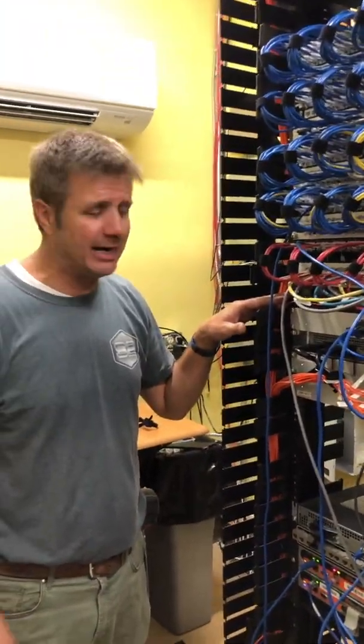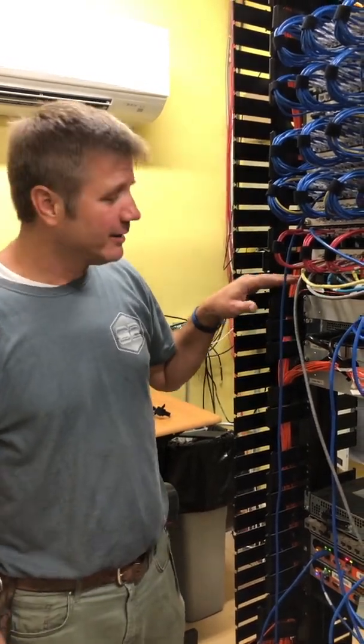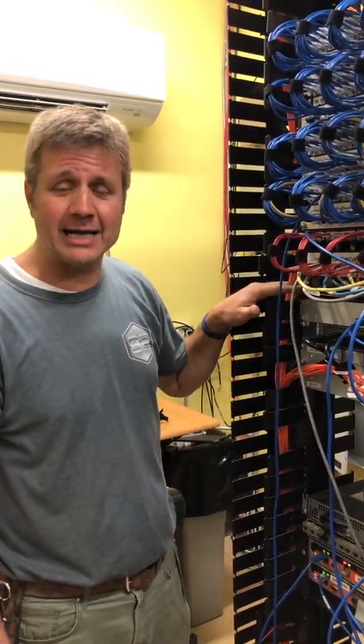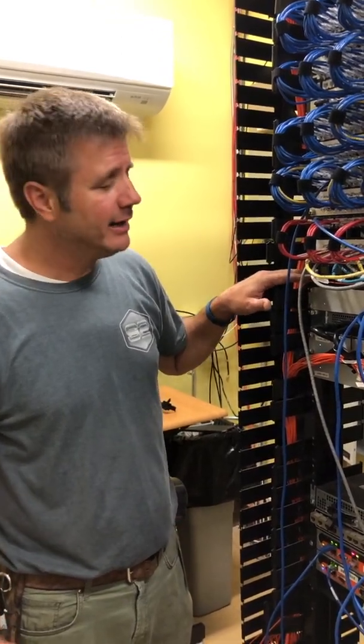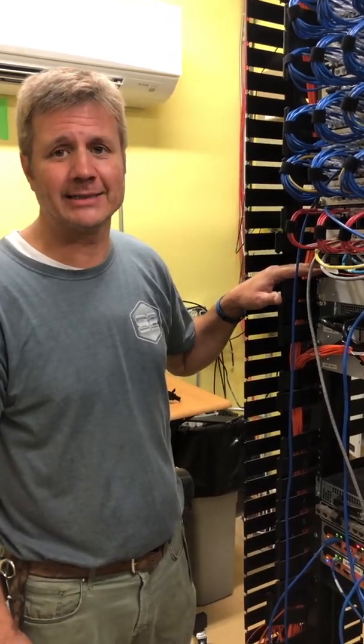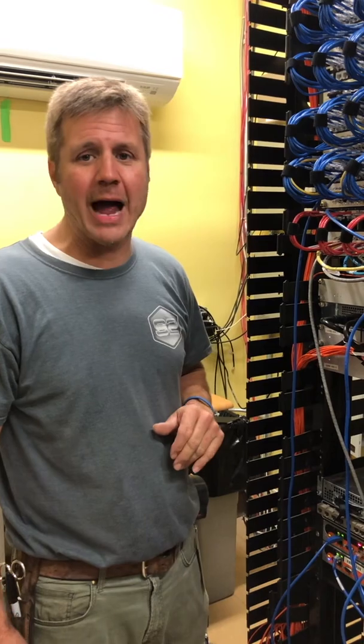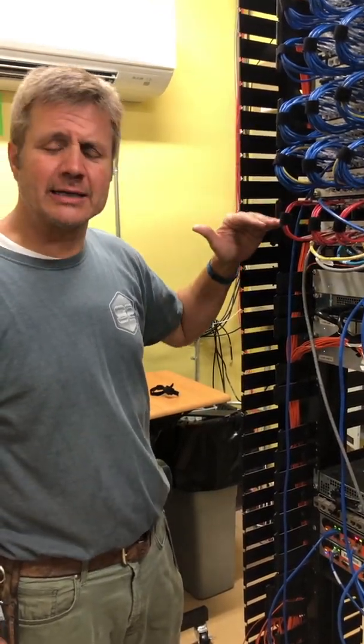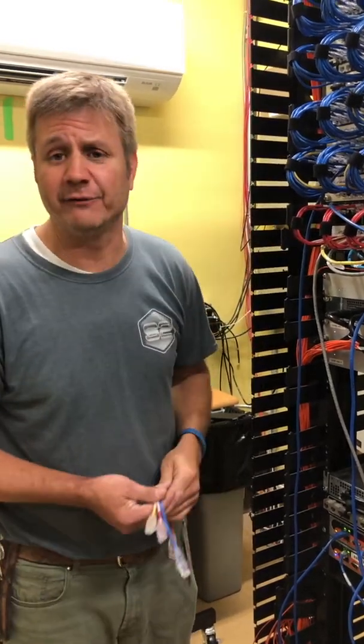The purpose of that was two-fold. Number one, make sure whoever puts in the jacks gets the right equipment — the right product line that they're already using. And two, as a space saver — because if you don't put a placeholder at the location you want to save for the future in the rack, it's going to happen: someone else is going to come in and place some device there, and that's going to throw it right back out of whack.